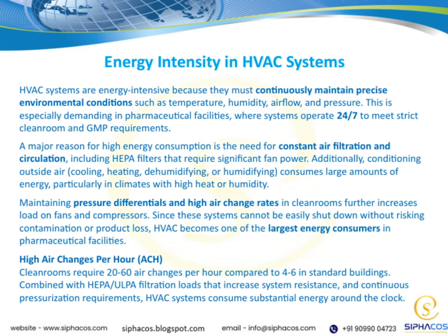Now, when it comes to air changes, cleanrooms typically need between 20 to 60 air changes per hour, compared to just 4 to 6 in standard buildings. When you add the resistance created by HEPA or ULPA filters, along with the constant pressurization requirements, it really ramps up energy consumption around the clock.